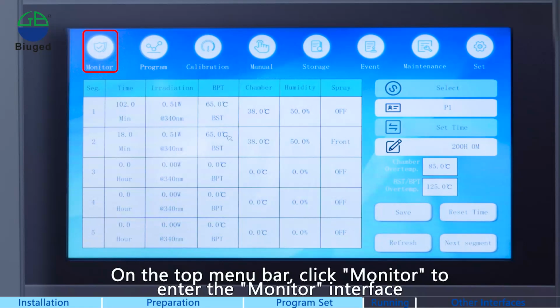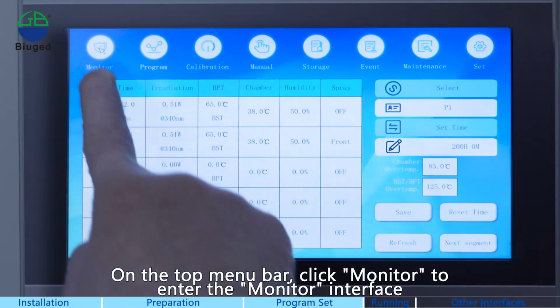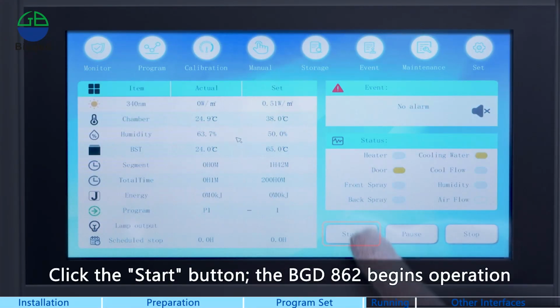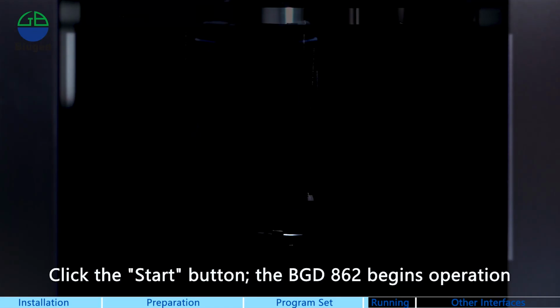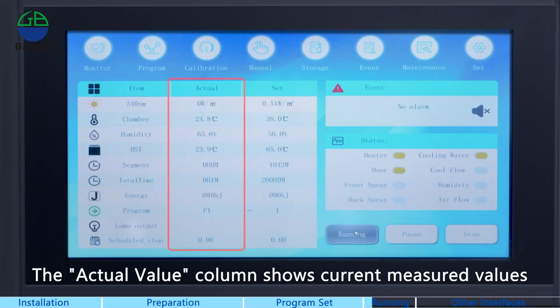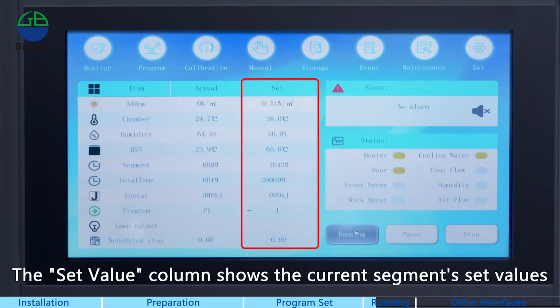On the top menu bar, click Monitor to enter the monitoring interface. Click the Start button. The BGD 862 begins operation. The chamber operates towards the set target values. The Actual Value column shows current measured values. The Set Value column shows the current segment's set values.